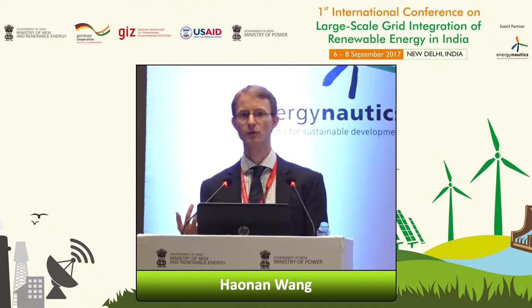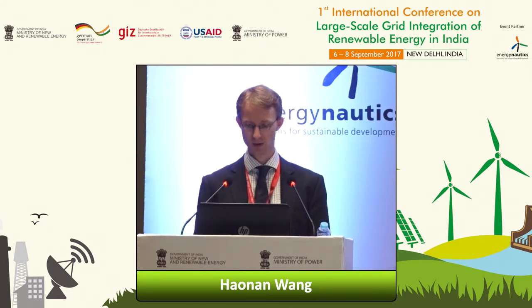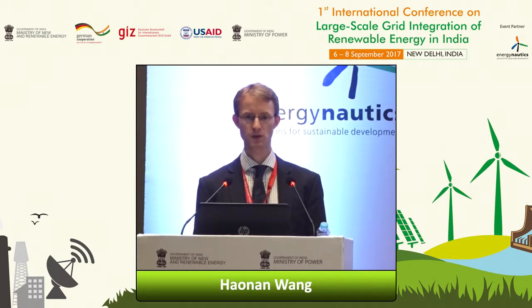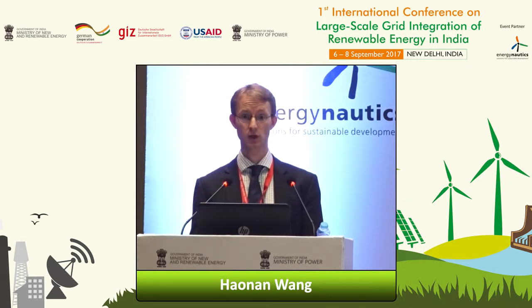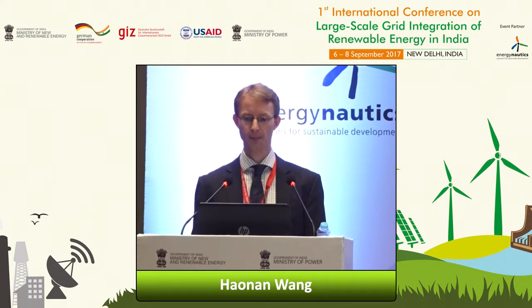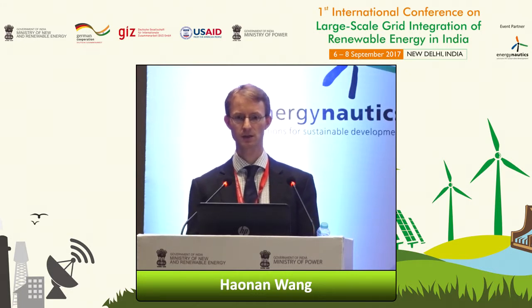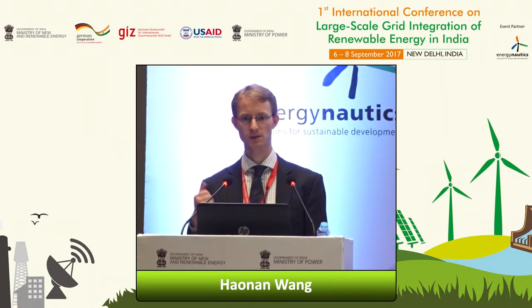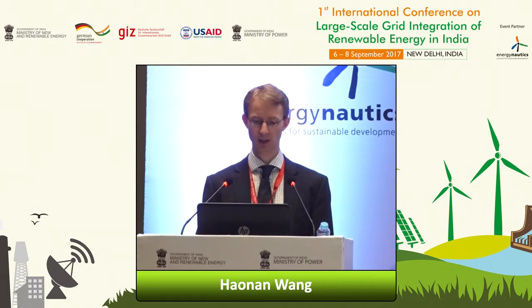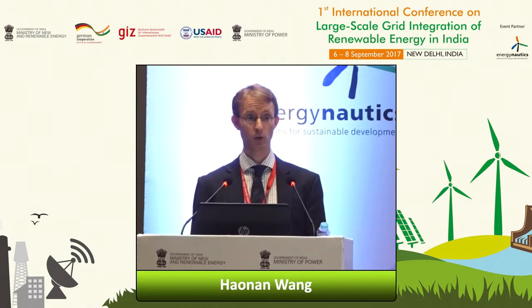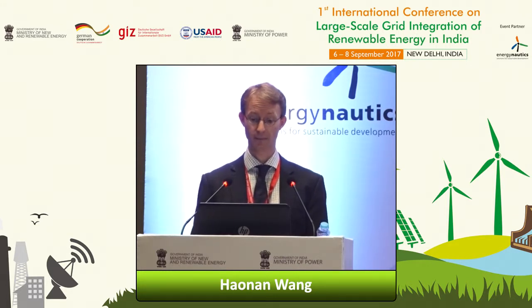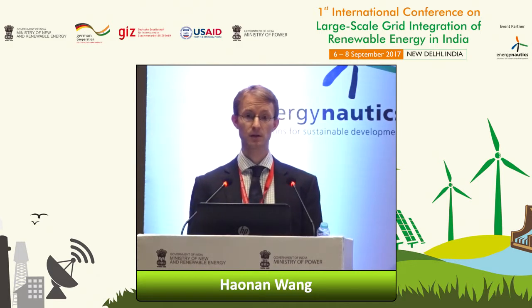So we can consider different control concepts. One is, as you can see on the right-hand side, local control. This means I only have a local measurement of voltage, and I do reactive power or active power control. Here we keep to reactive power in order to stabilize the system. I can also do it on the left-hand side by central control. In the control center, I have the ICT equipment, and I can run a central optimization function and apply it throughout the system. There we are going into the digitalization area, which I showed at the beginning. Then in the middle, the decentral way.